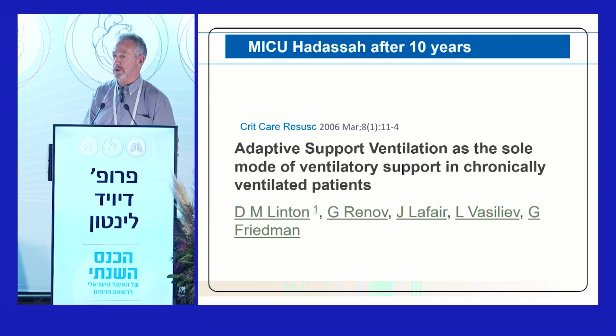What was the secret? The secret was the ingenuity of Professor Joseph Brunner, who worked with a guy called Wolf and published the first book on measurement of lung function, not in the lung function laboratory, that you could measure lung function online with a flow sensor. The flow sensor has a diaphragm, 2 pressures. It measures every parameter of inspired air and expired air, pressures, flows, time constant of the lung, any parameter you can measure in the lung, and it goes into a computer. The prototype we researched in South Africa was a PC with a Macintosh computer driving the Hamilton Amadeus ventilator. That was the prototype. We did the original research, and that was the start of automation in ventilation worldwide.